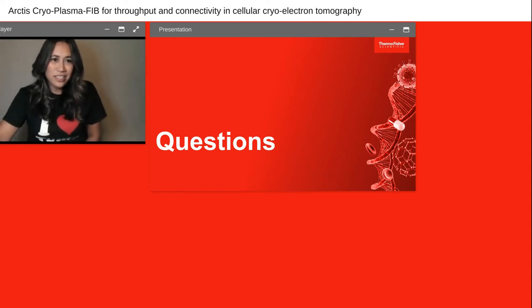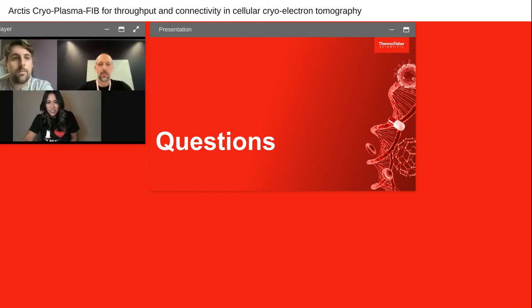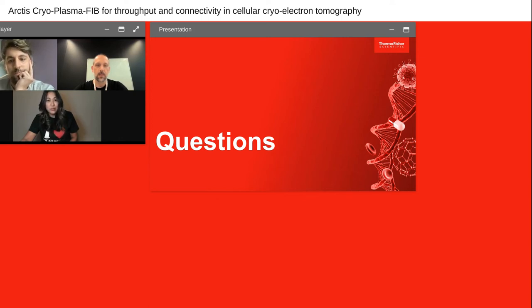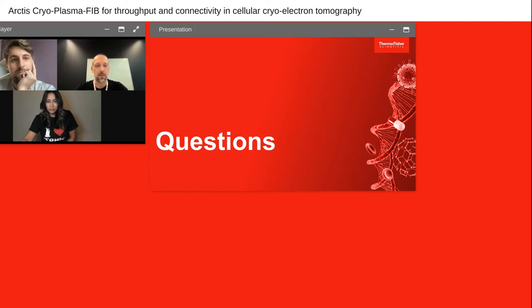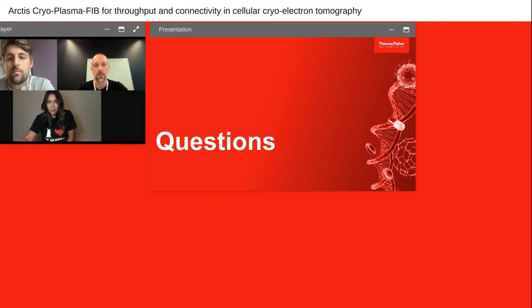Thank you gentlemen for the great presentations. We have a few questions. The first: is it necessary to cryo-cycle the Arctis frequently? Does debris accumulate on the sample? You have to do it once a week — not much different from TEM systems. Once a week, warming it up and re-cycling is sufficient. There are a lot of cold surfaces inside which trap contaminants from the milling. It means the system can run autonomously for a week on the nitrogen dewar.